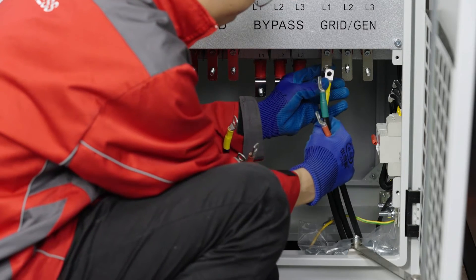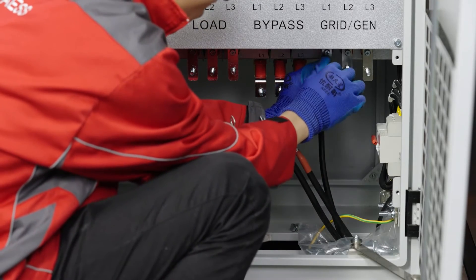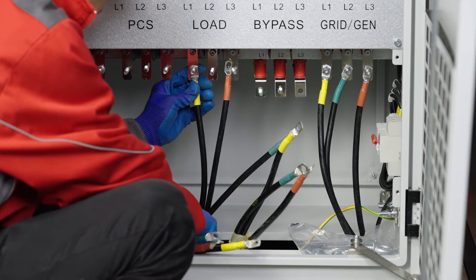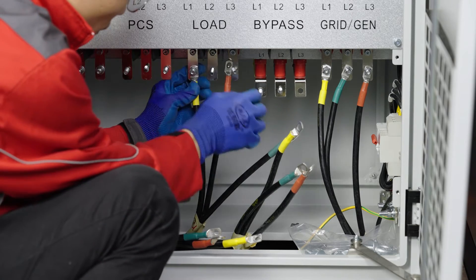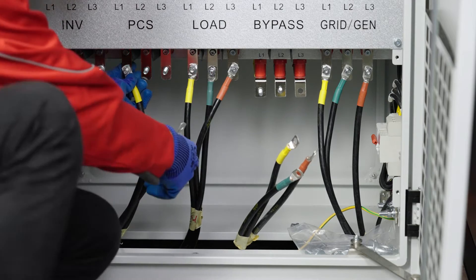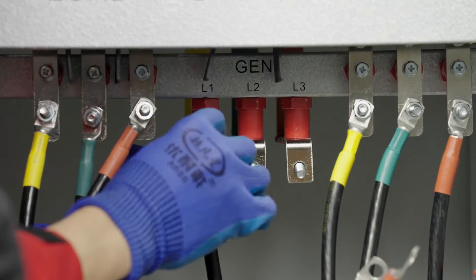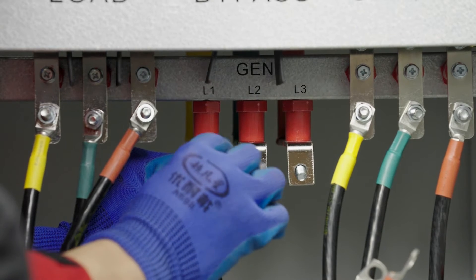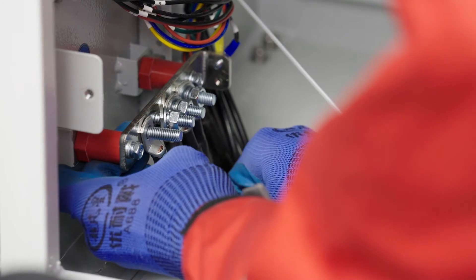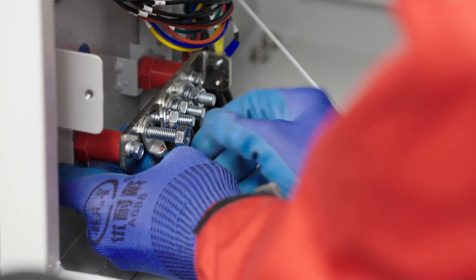Connect the grid wire to the grid terminal of the bypass, paying attention to the phase sequence. Connect PCS cables to the PCS port of the bypass in the correct phase sequence. Connect the generator wire to the GEN port of the bypass in the correct phase sequence. Connect the ground wires of the power grid, diesel generator, load, and PCS to the ground bar of the bypass.